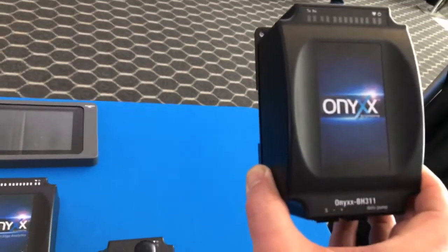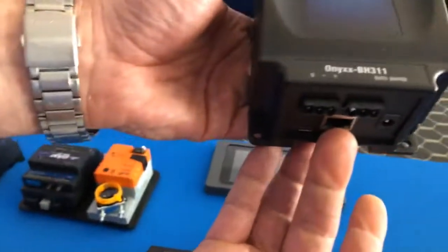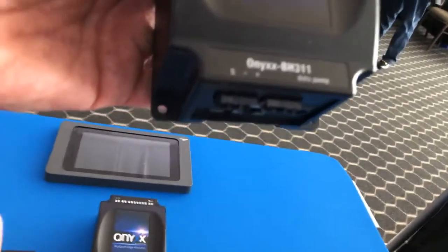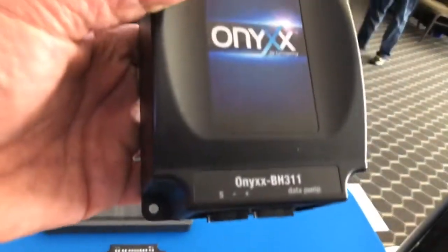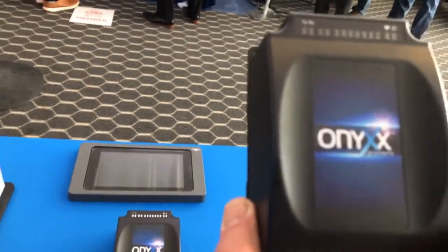So you have to power this bad boy up. How do we hook this thing up? Power it up. It has one Ethernet port, so that's a challenge for some folks. They'd like to have two, but just plug it into an existing switch, and you're off to go. You can connect to it with your computer. Open up a browser, log into it, configure it, discover the BACnet, and push them out to Haystack.